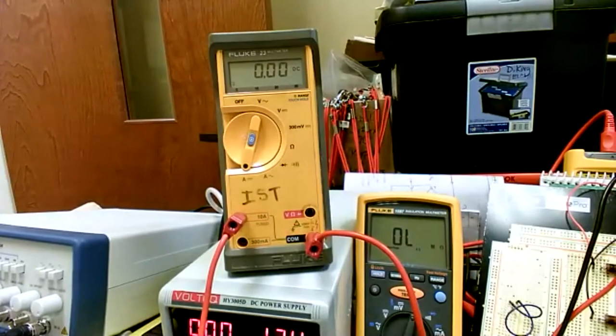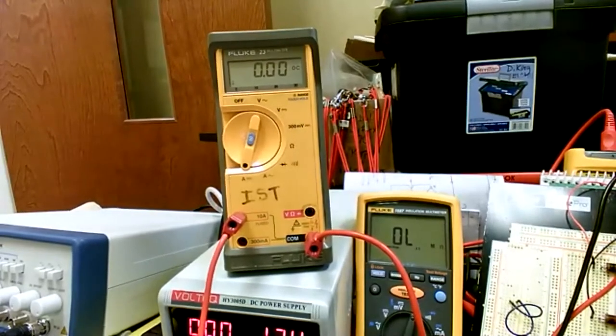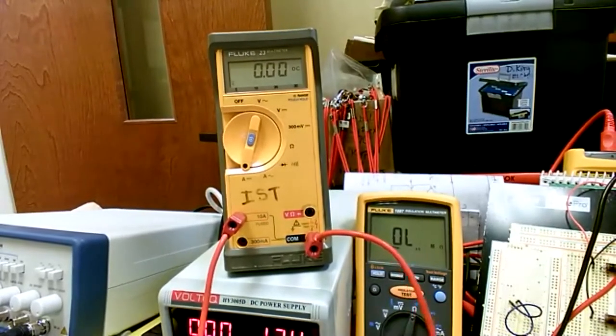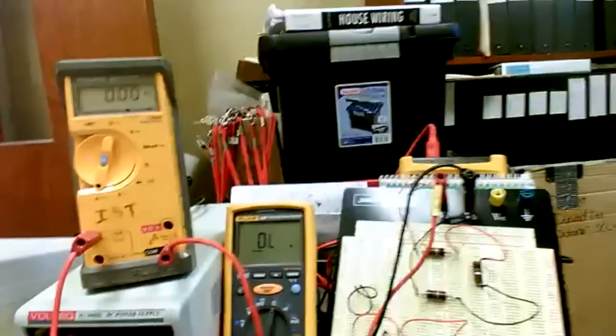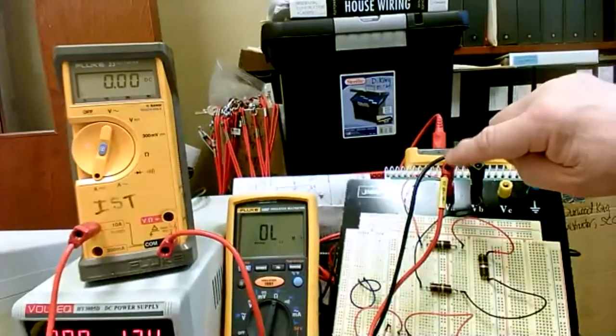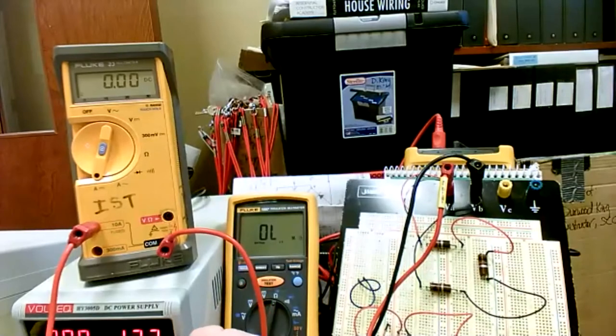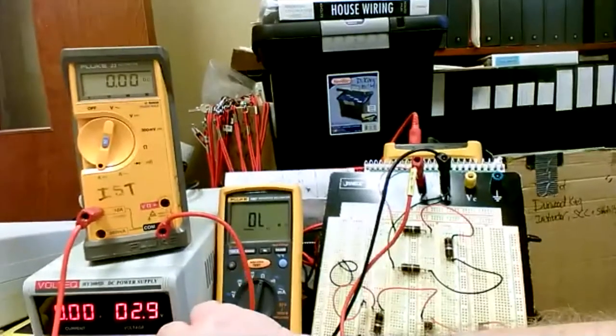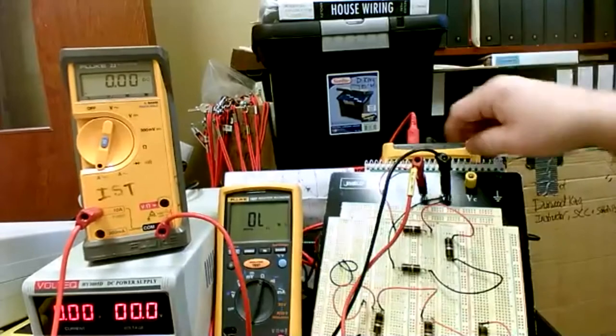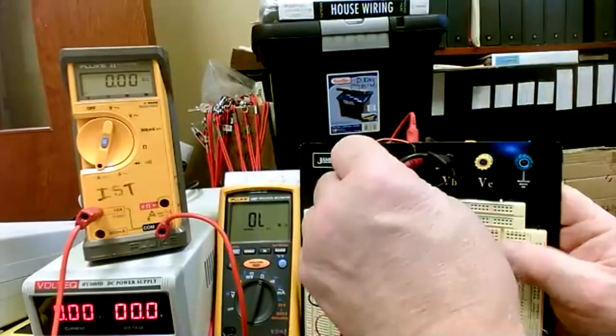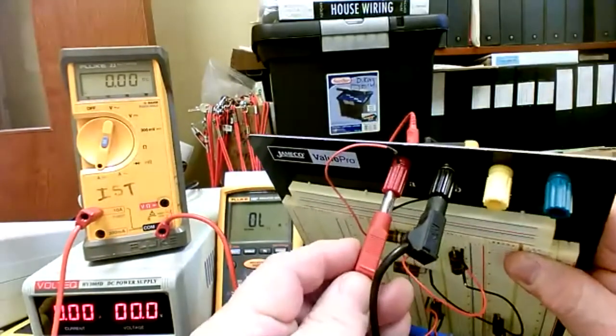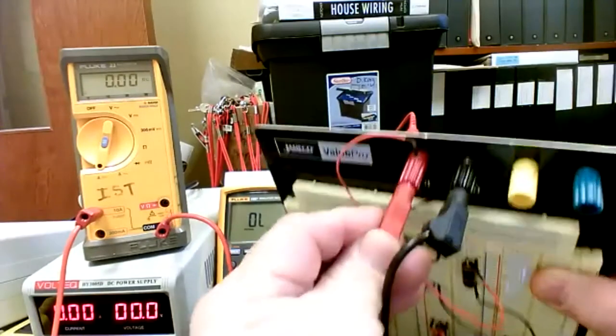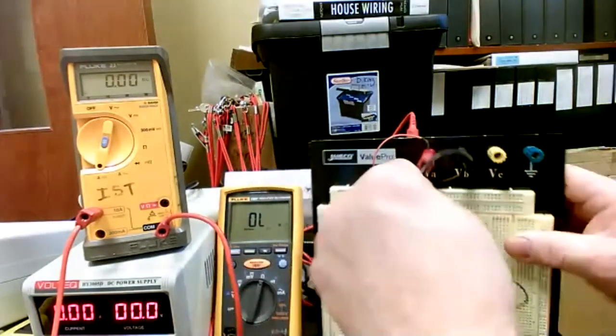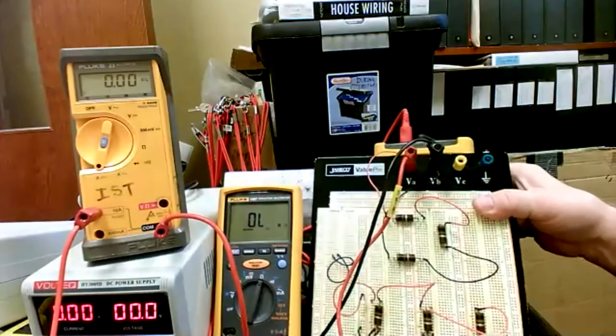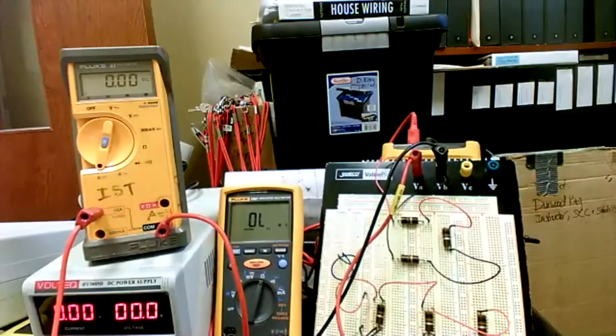And we're not reading anything in here. We must have a connection that's gone. This little red quick connect popped out of the board. So let's zero that back down. You see that? It popped out. That's why we weren't getting a current reading, because we didn't have a connection.